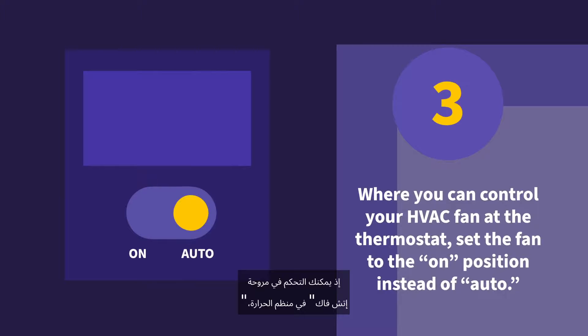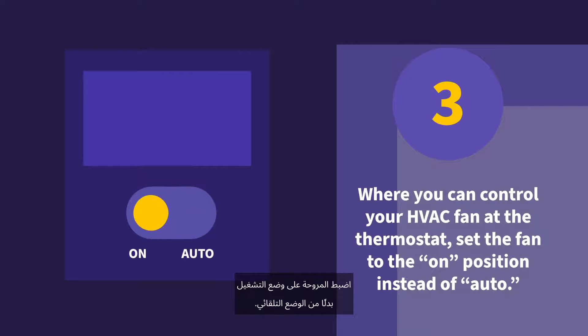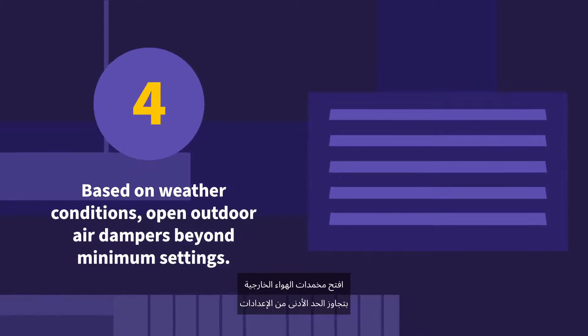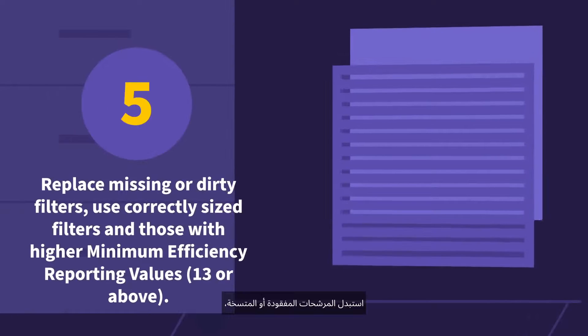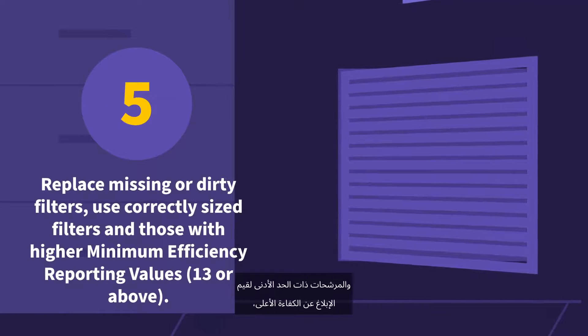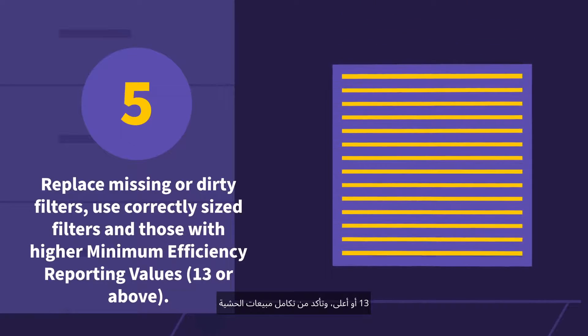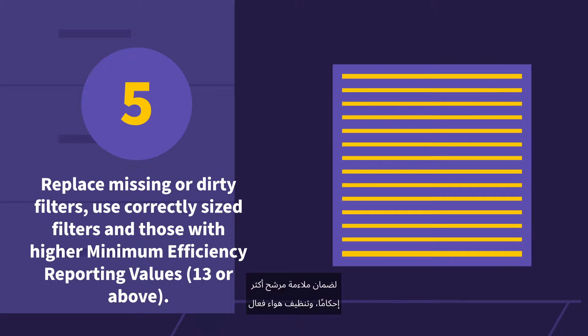Where you can control your HVAC fan at the thermostat, set the fan to the on position instead of auto. If possible, based on weather conditions, open outdoor air dampers beyond minimum settings to reduce HVAC air recirculation. Replace missing or dirty filters, use correctly sized filters and those with higher minimum efficiency reporting values — MERV 13 or above — and confirm gasket seal integrity to ensure a tighter filter fit, efficient air cleaning, and to prevent recirculation of infectious particles throughout the building.